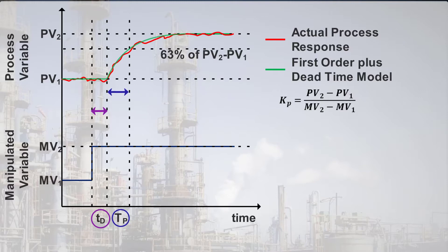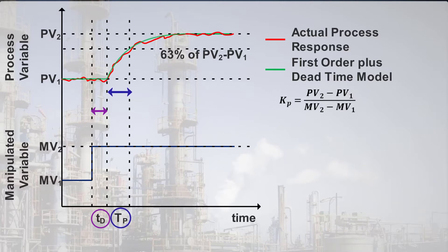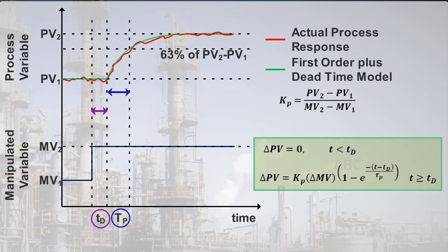The time constant, T sub P, is the time it takes the response to move 63%, or 1 minus e to the negative 1, of the way to steady-state — that is, it is the time constant of a first-order dynamic response. This is called a first-order plus dead-time dynamic model, which can approximate just about any actual dynamics that you will encounter in a real process.